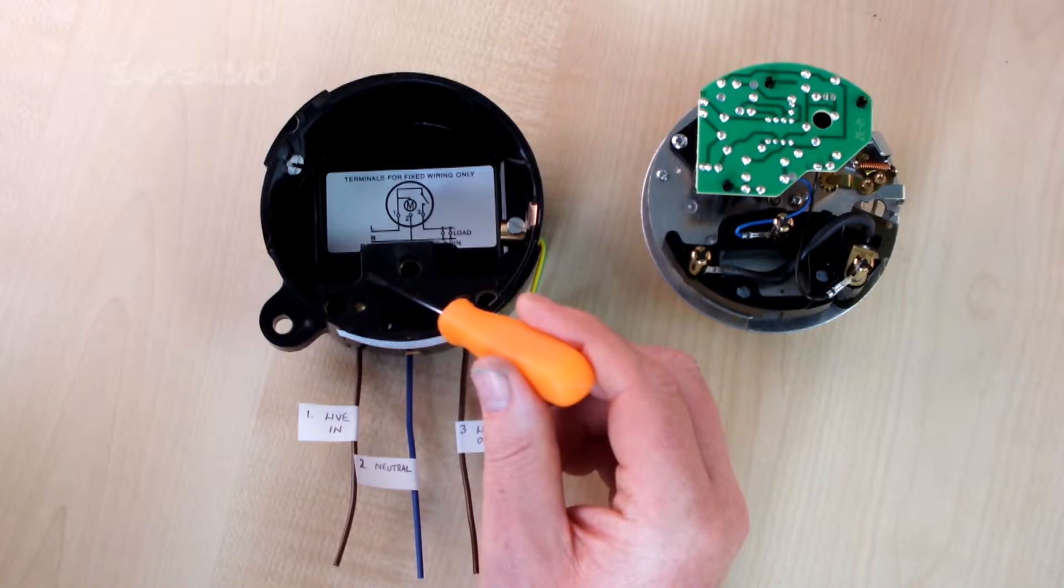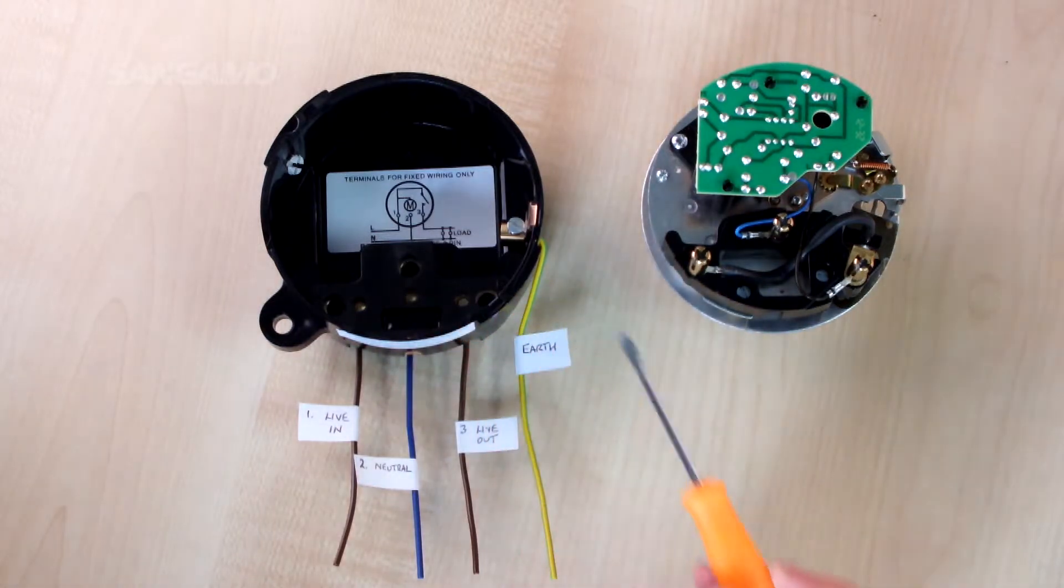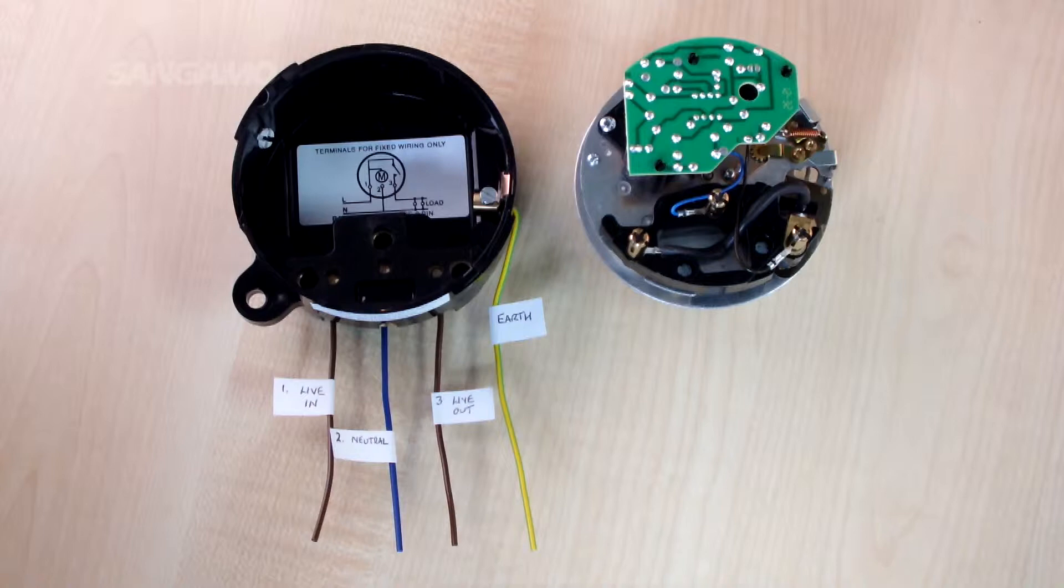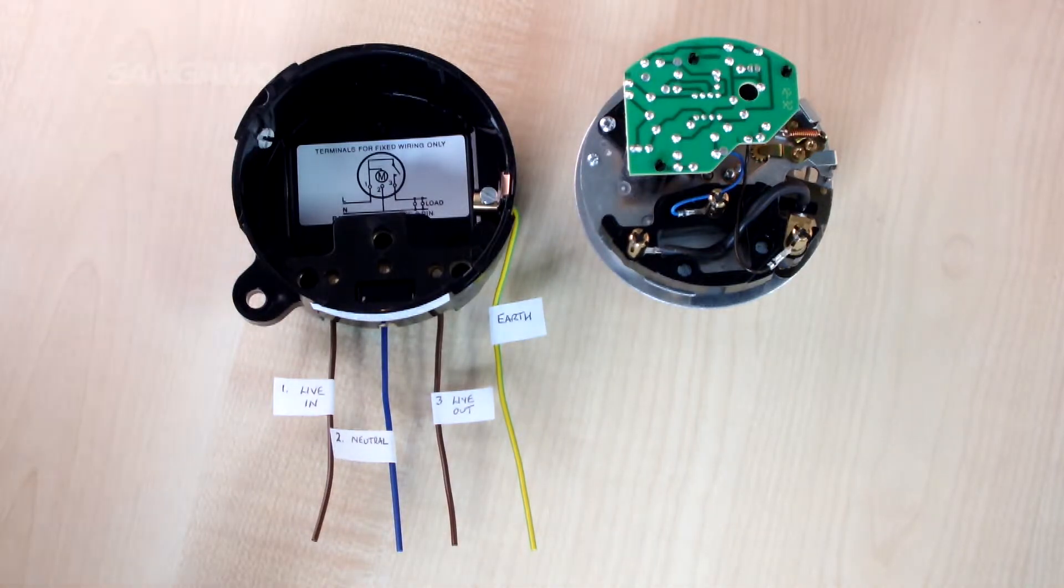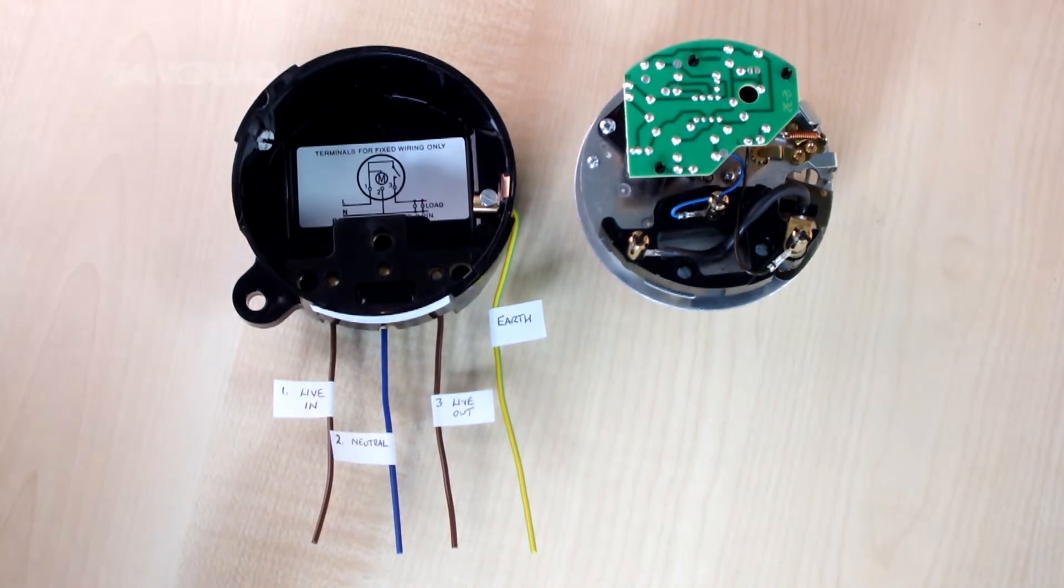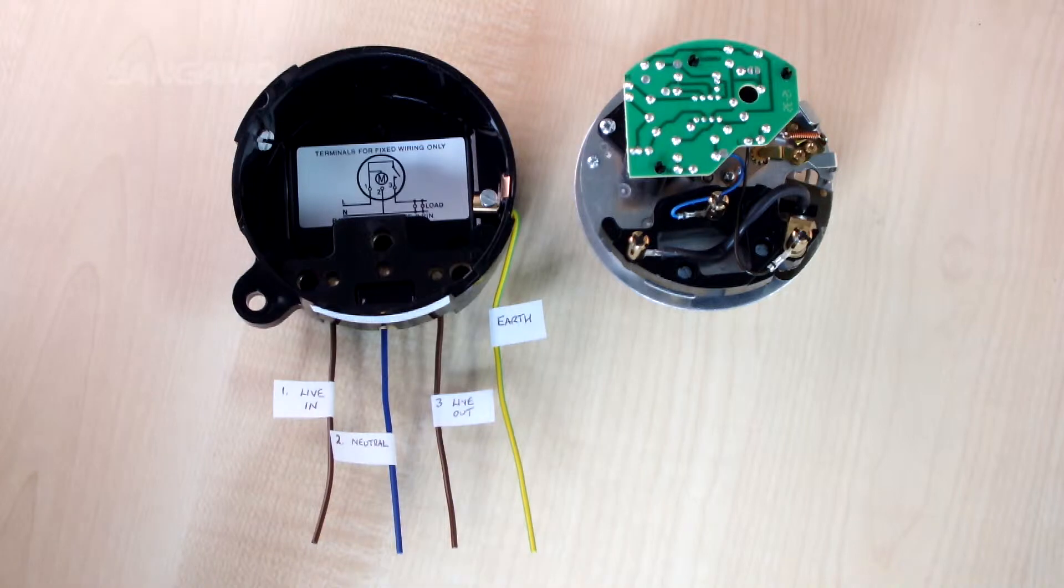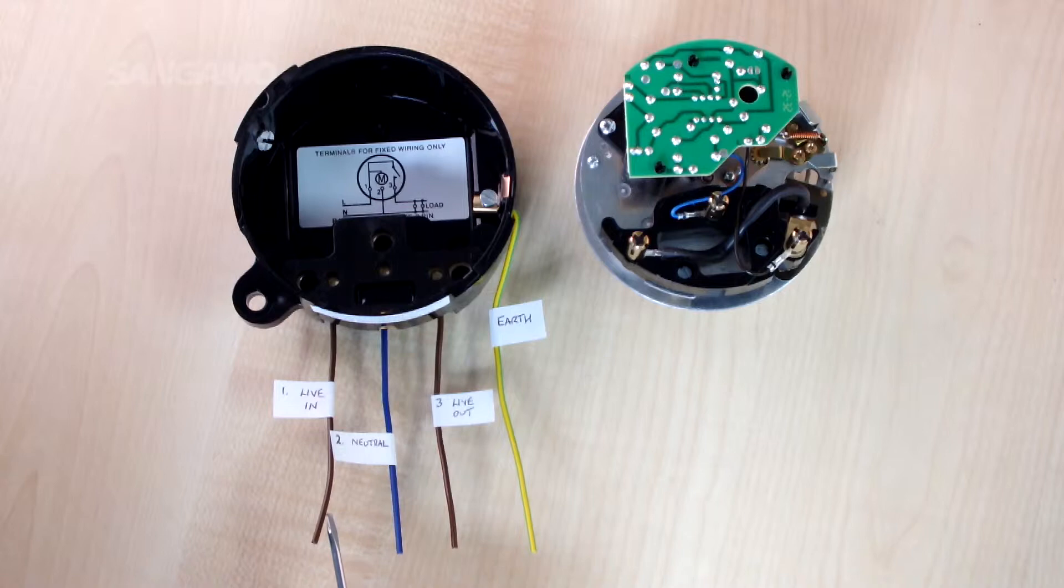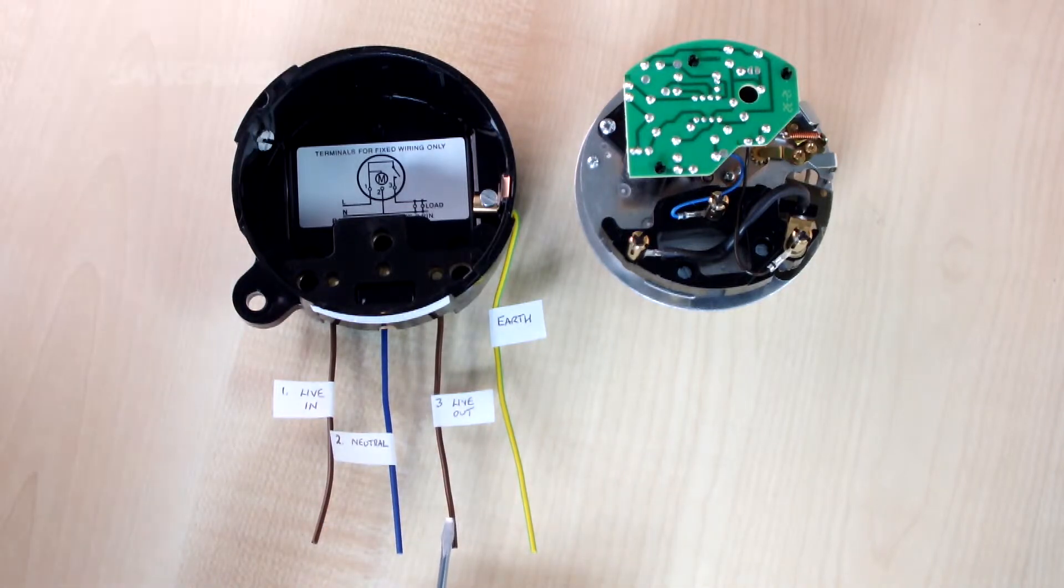If we start with 3 pin time switches, these are for 230 volt applications only where a common live supply is being used to operate the clock and also provide an input for the switching circuit. In terms of wiring, you would have a live into terminal 1, a live out from terminal 3.